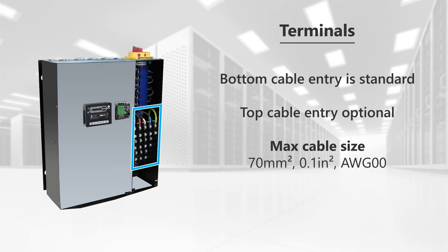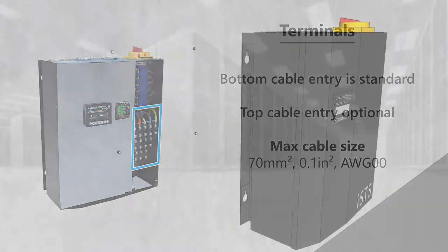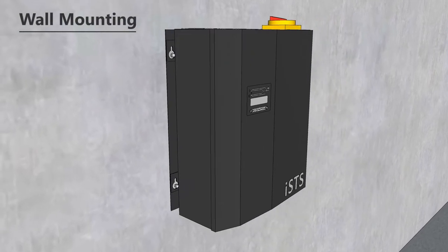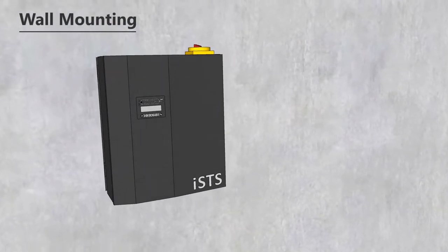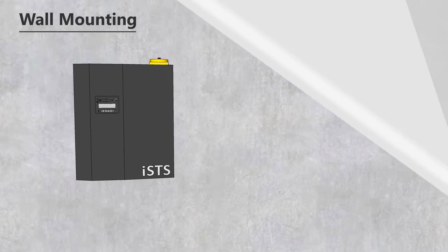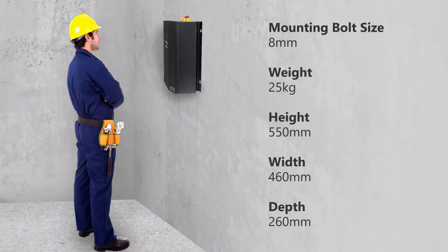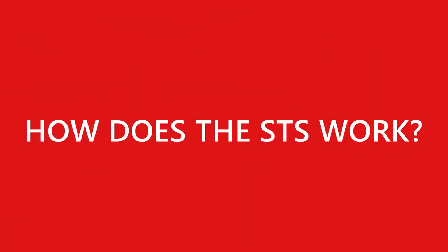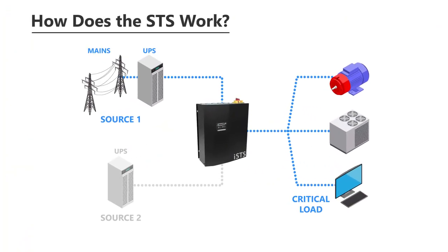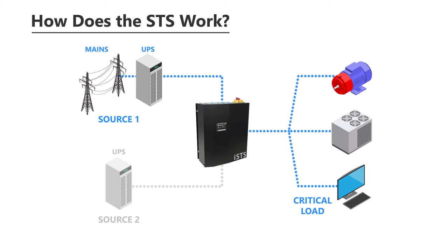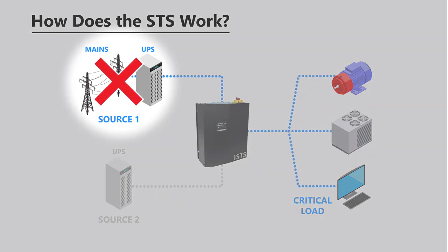Bottom cable entry is standard, with top cable entry available as an option. Terminals suit bolted lug connections using cables up to 70 millimetres squared. The Model W mounts conveniently to the wall using eight-millimetre bolts. The STS connects one of two AC power sources to the critical load and provides secure power redundancy.